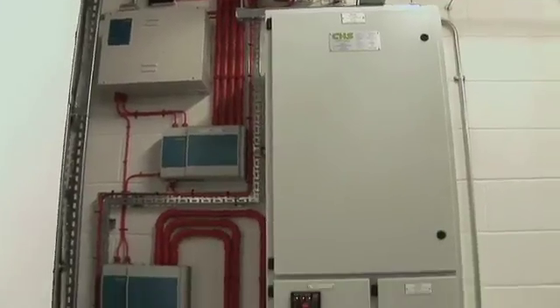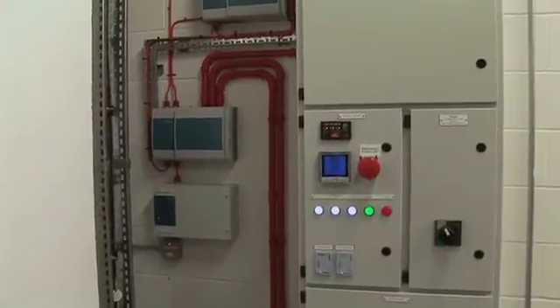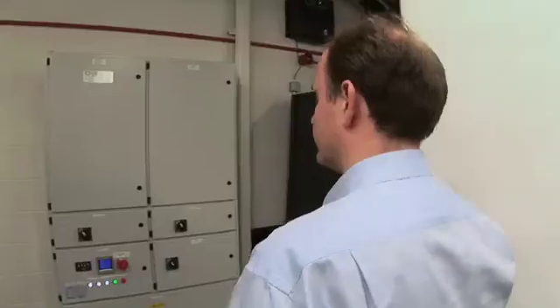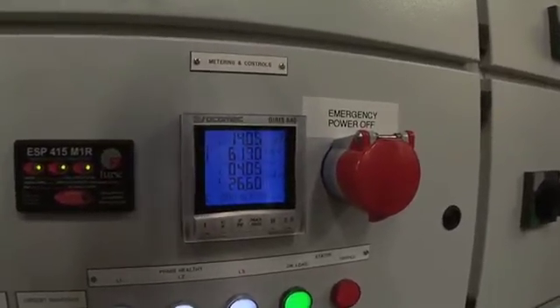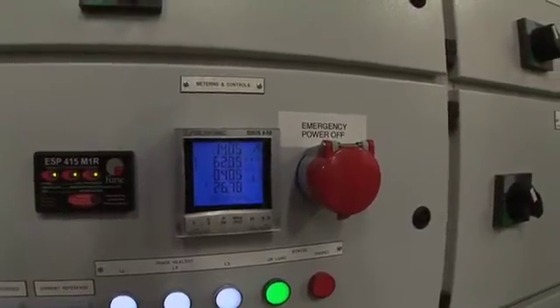As you'd expect with a data centre, we use a lot of power and all of that power is distributed using one of these four PDU units. These all go back to a central UPS pair, and each UPS is 250 kVA three-phase with 30 minutes of autonomy on the batteries. This allows us to provide six amps of power to every rack in the room.